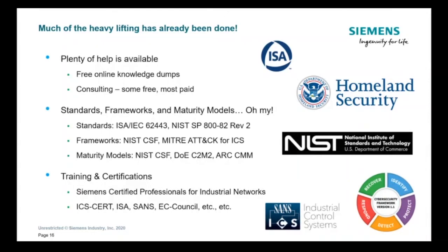One of the more common ones is the IEC 62443. That is a global standard that's in place that many people, especially manufacturing locations, take advantage of. Then there's also the NIST 800-82 standard as well. That standard typically is used in any critical infrastructure type place or anything that has any government regulation in the US. That could be power generation, power distribution, water, wastewater.